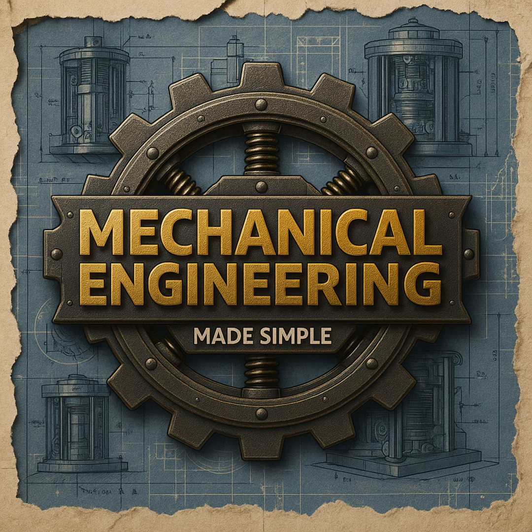So how do designers account for that when they're sizing rectangular ducts? They use a concept called the equivalent diameter, usually written as D sub E. There's a specific formula for it. D sub E equals 1.3 times (A times B) raised to the power of 5/8, all divided by (A plus B) raised to the power of 1/4, where A and B are the side lengths of the rectangle. Okay, a bit complex, but the point is...